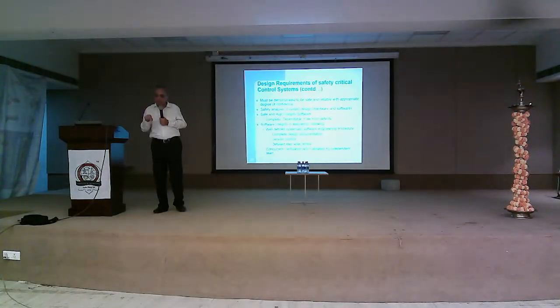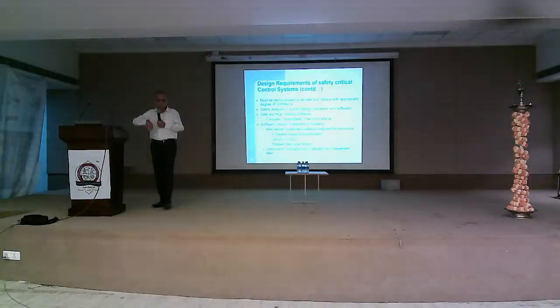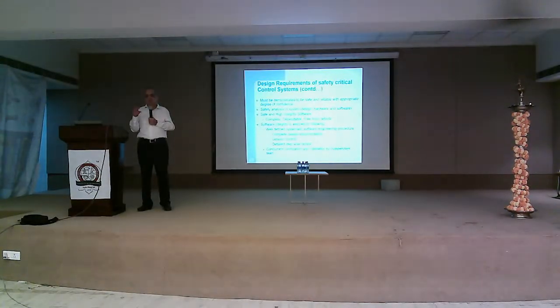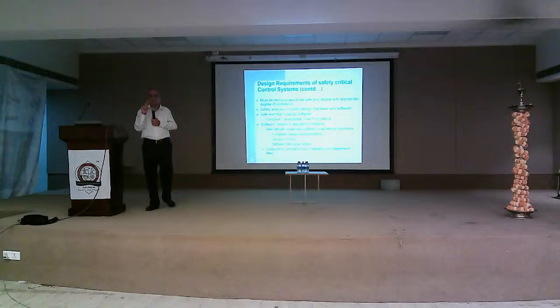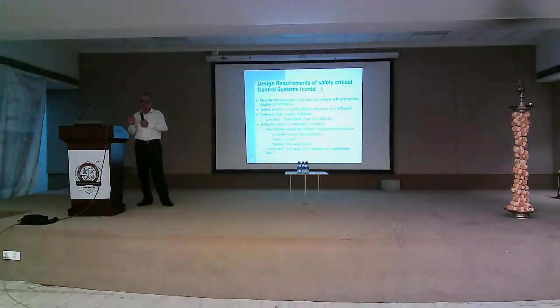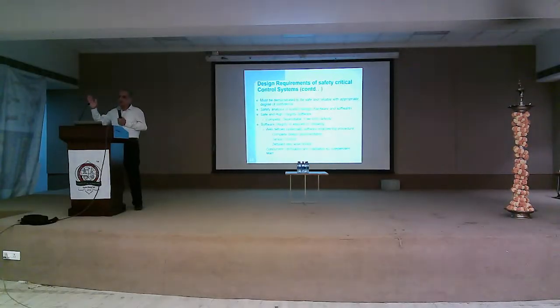software modification is much more costly. Because afterwards you find out, you will redo the job, a lot of money is involved, a lot of time is involved, and more than that, during patchwork you may introduce some more errors. So right from the beginning, you have to make sure that the software requirement specification is complete, unambiguous, and dependable. And for each requirement we make a matrix, software requirement to system requirement, matching one to one, and nothing is extra.